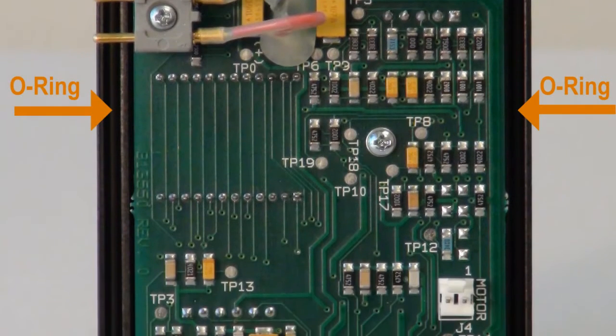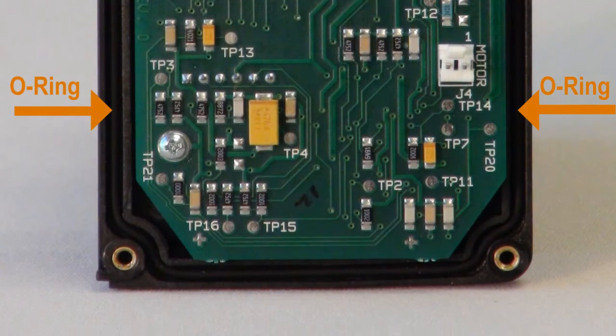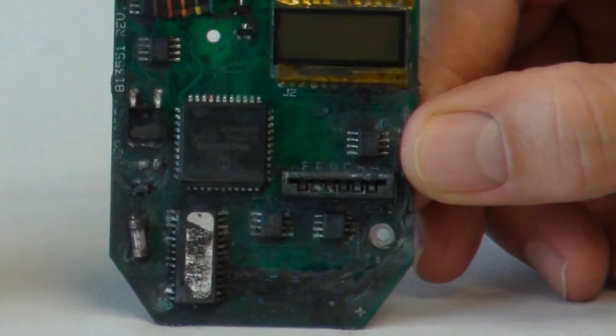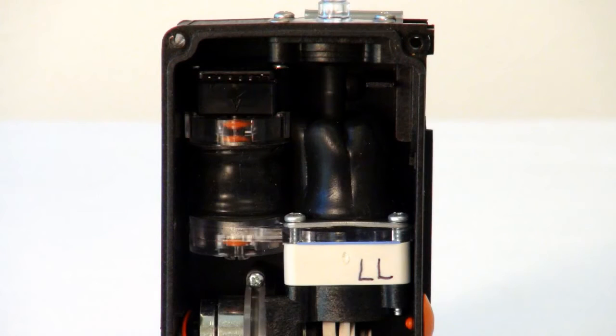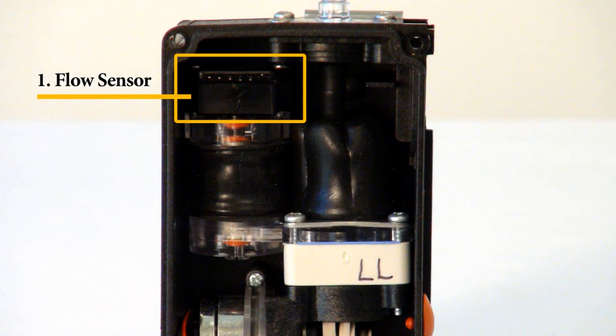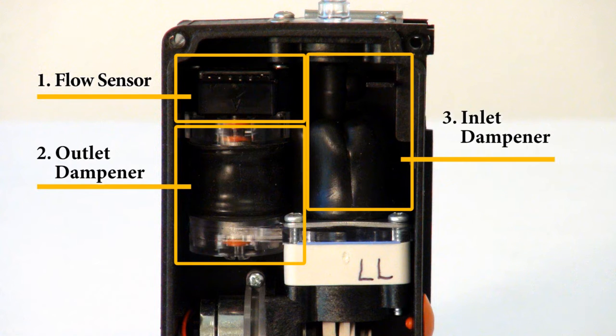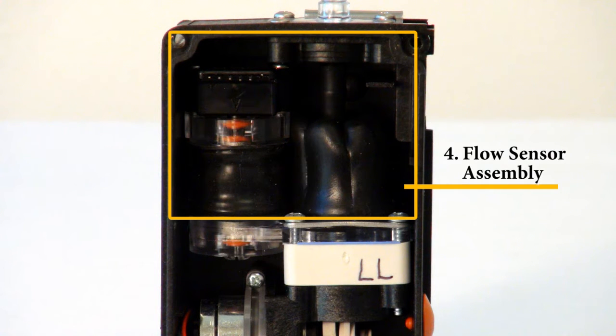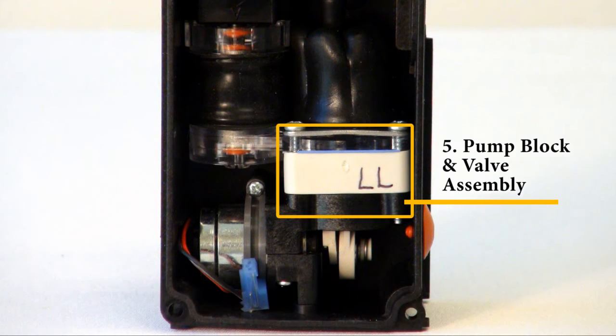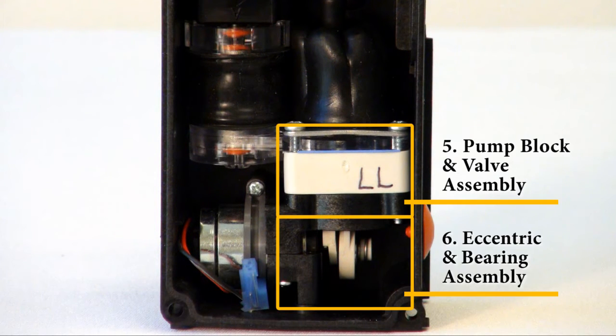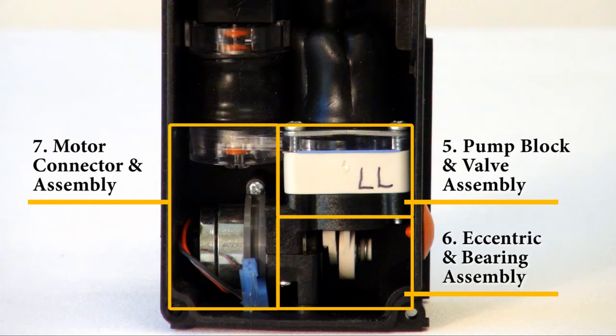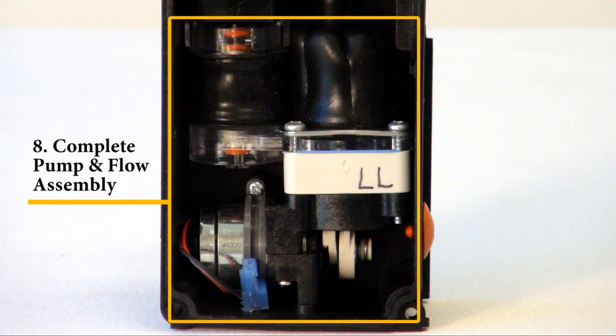It is very important that the O-ring around the inside of the faceplate is properly installed and not damaged. A damaged O-ring can lead to severe pump damage as shown on this circuit board. The internal parts of the pump and flow assemblies are flow sensor, outlet dampener, inlet dampener, flow sensor assembly, pump block and valve assembly, eccentric and bearing assembly, motor connector and assembly, complete pump and flow assembly.